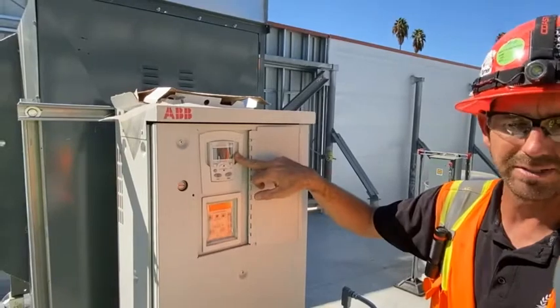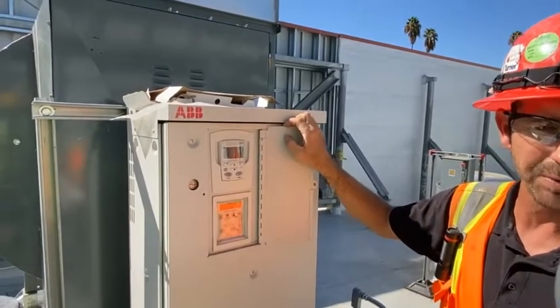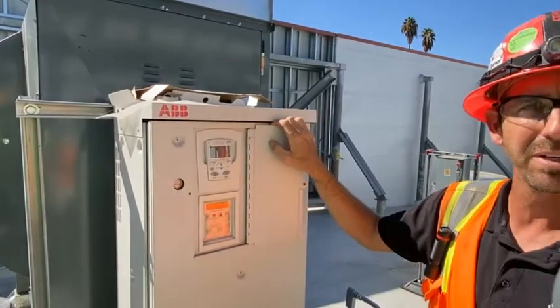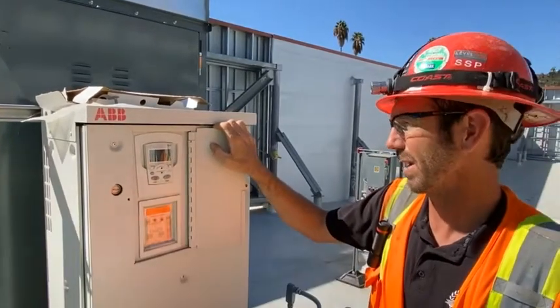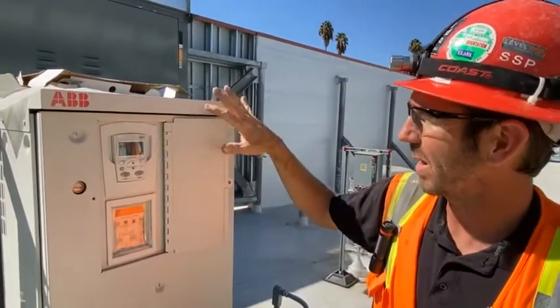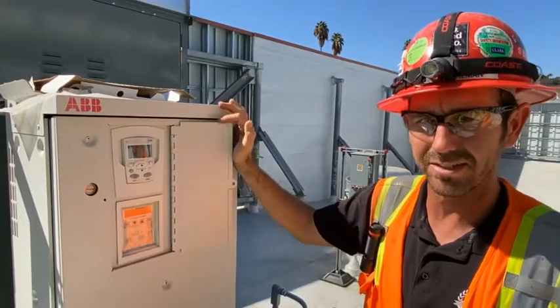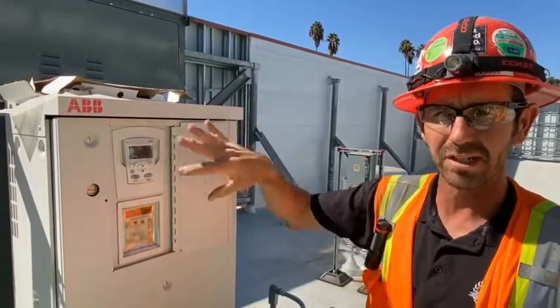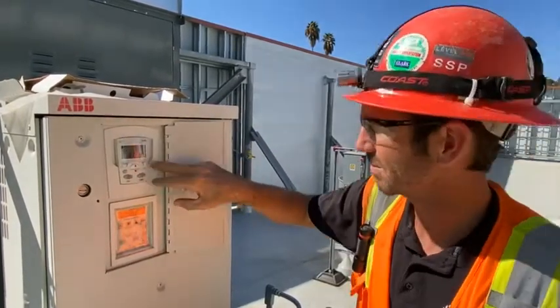The VFD's already been set up for the motor horsepower, the amperage, the voltage, and the RPM of the motor. The fan will ramp up and ramp down. This system right here is pretty basic. It's just an easy starter that allowed us to lock in a certain speed for the fan to run.